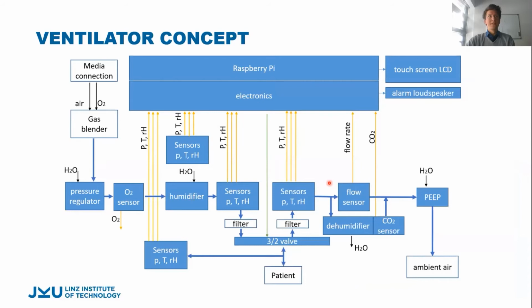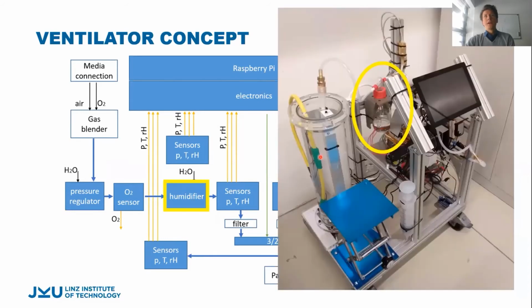We also have the humidifier. Air coming out of the pressure regulator is very dry, so we have to humidify it by letting it pass through a glass bottle filled with water. The air bubbles through the water and gets humidified. You also need to heat it because of the vaporization enthalpy, heating it to about 36 or 37 degrees, to apply warm and humid air to the patient.